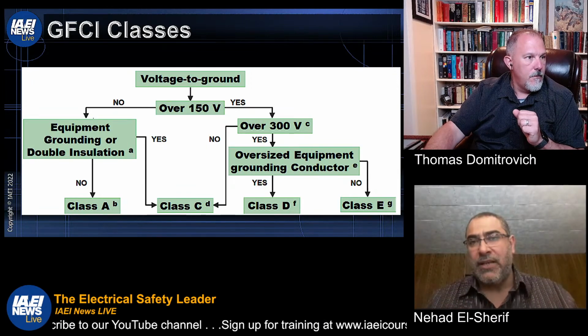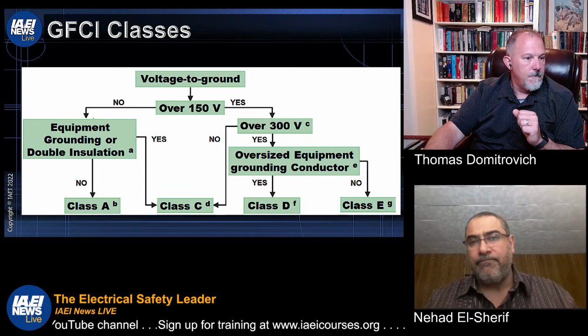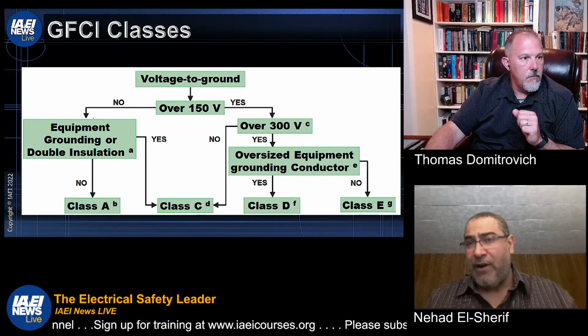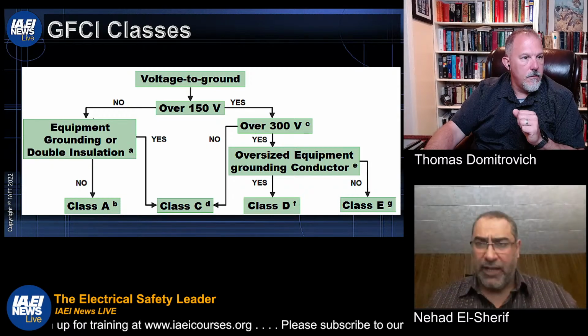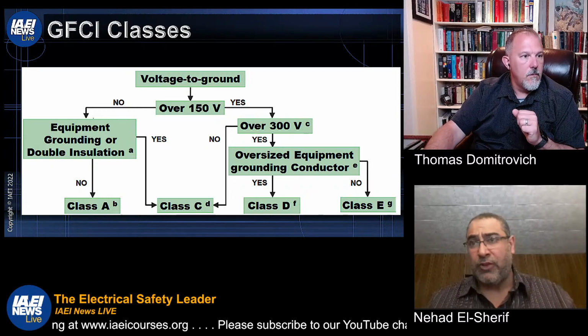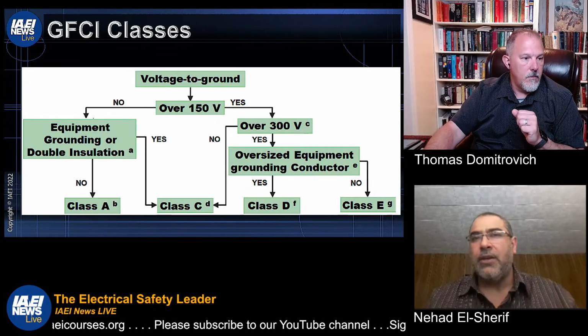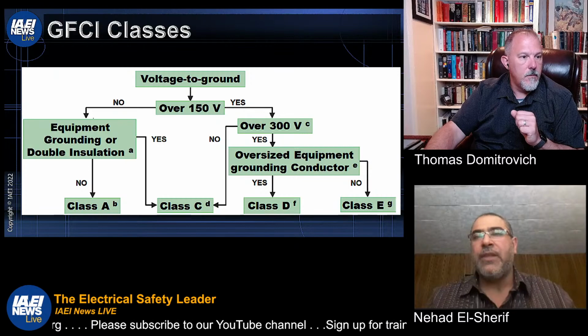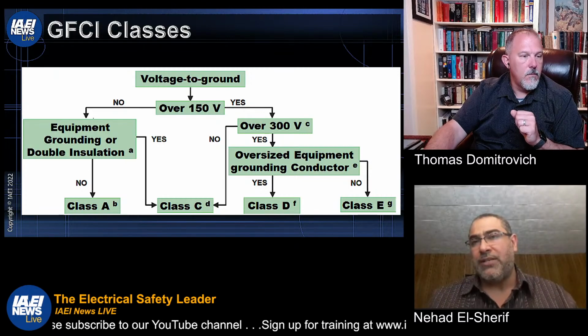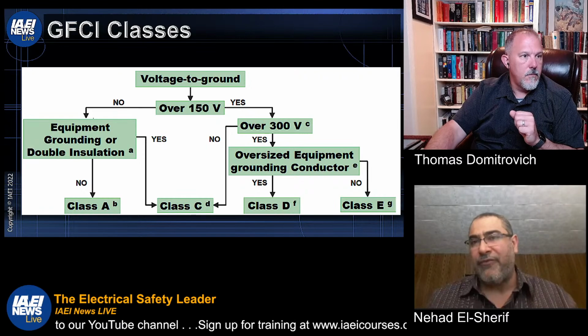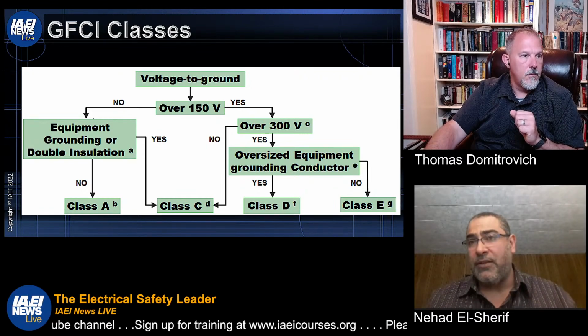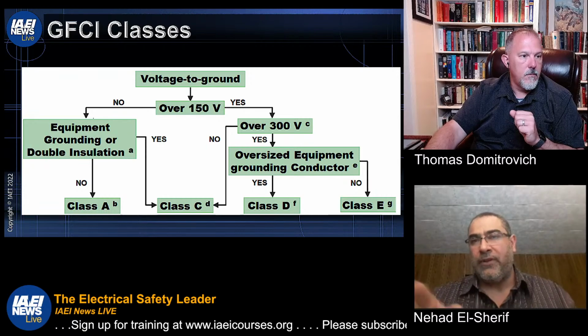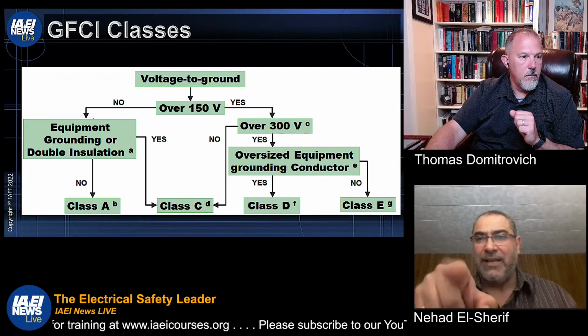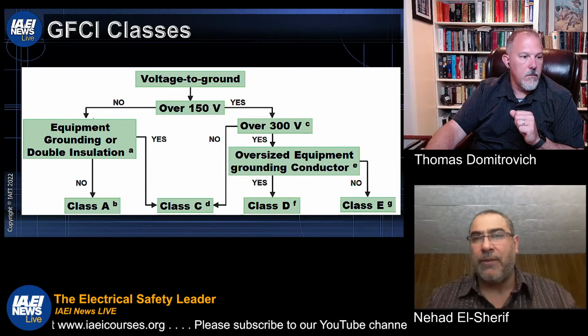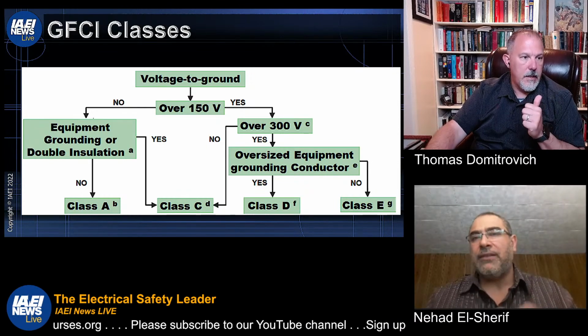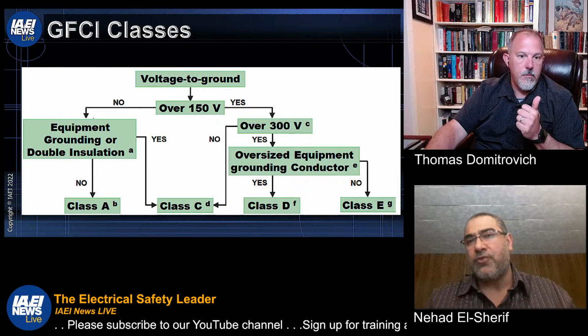The only exception is if you are using double insulated equipment or equipment grounding is required, which is something that you don't see at home. Like you don't have an equipment grounding conductor for your toaster, for example, or dryer, right? So this is the Class A area. But if you have those requirements, and your voltage to ground is less than 150, and you require equipment grounding, then Class C is your go-to, if you follow the no to the left and then yes for the equipment grounding, insulation, and double insulation requirement. But let's just go to the right-hand side of the chart, which is over 150 volts.